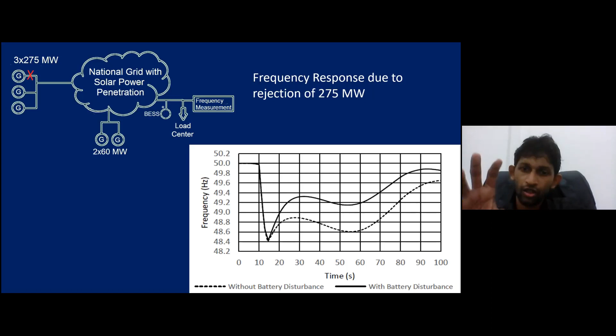Now, the other thing which I did was, I incorporated a unity power factor generator with zero inertia, which comes into play as soon as a contingency occurs, a virtual synchronous generator. Now see what happens here. In the same manner, with the battery energy storage system and without the battery energy storage system, the recovery and final frequency response is better off when there is a battery energy storage system. But is there load shedding? Yes, there is load shedding.